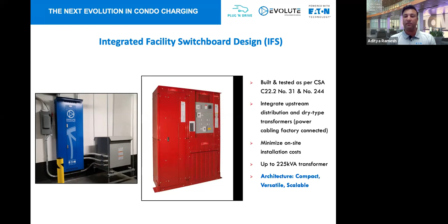That ties back into that compact, versatile, and scalable solution, really useful for new buildings, especially where you want to keep the overall footprint of the electrical distribution system as compact as possible, and even have the EV panels within the electrical room itself, then run conduit and cable out to the specific parking spots in the garage. In terms of the transformer, you can have up to a 225 kVA transformer within the enclosure itself.